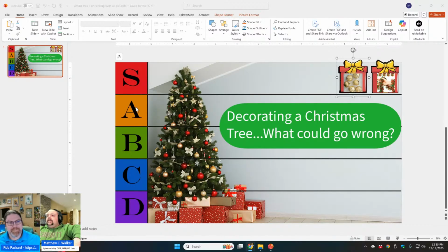Okay. If we were looking at this like a use-related risk analysis, where would we draw the line for a critical task? Right between A and B. If it requires medical attention, it's a 3 or a B, C, D. Those are going to be the ones that you have to report to the FDA, and those are the most serious. Those are also the critical tasks. Critical tasks would be something that will actually result in harm. Whereas the 1s and 2s, those are not something that would require reporting, and they wouldn't be considered a critical task.